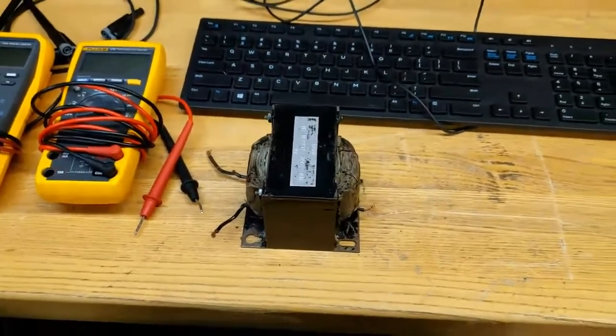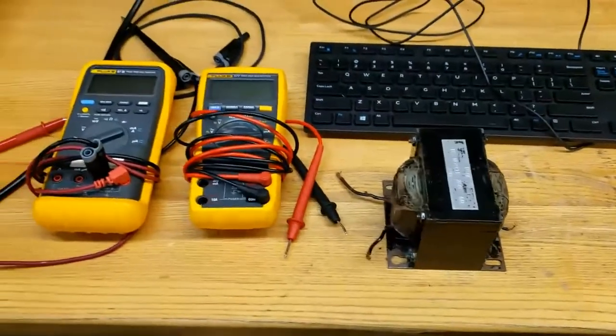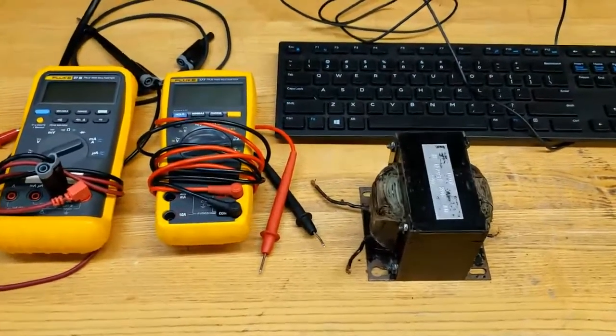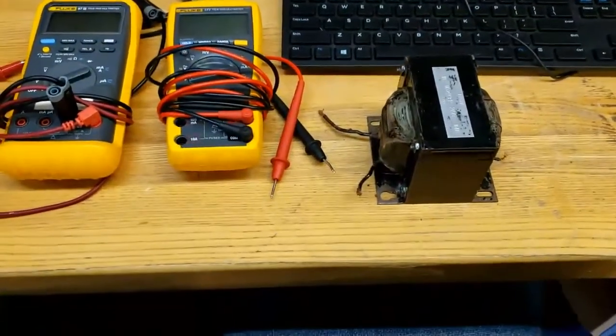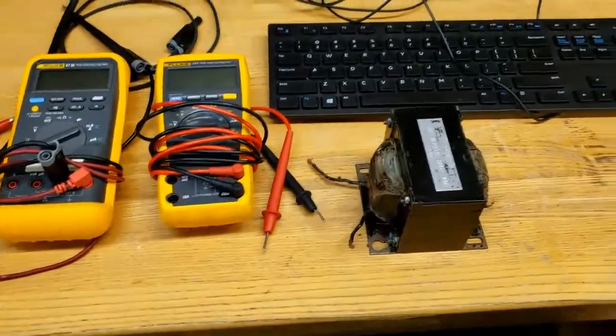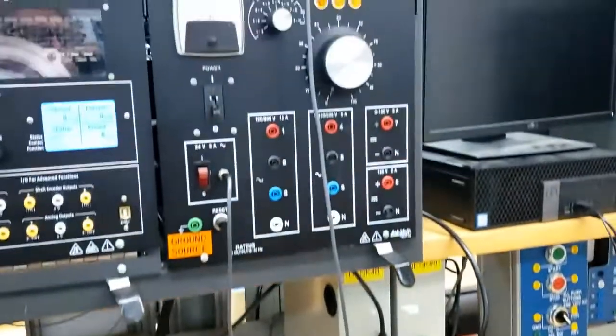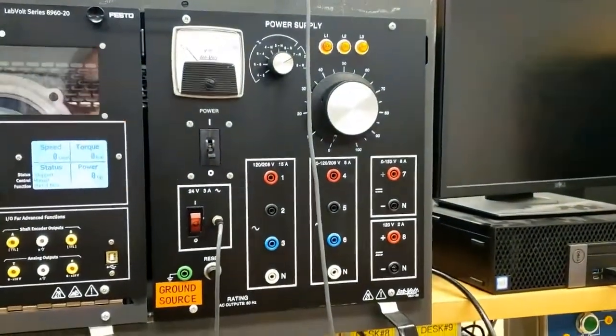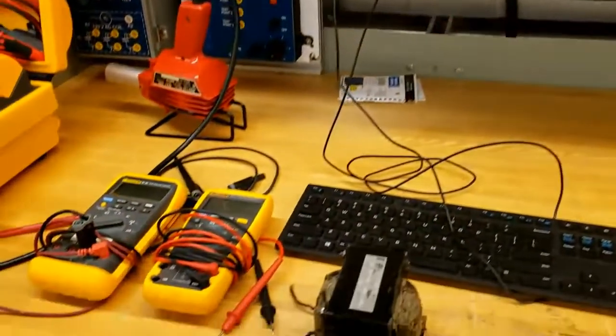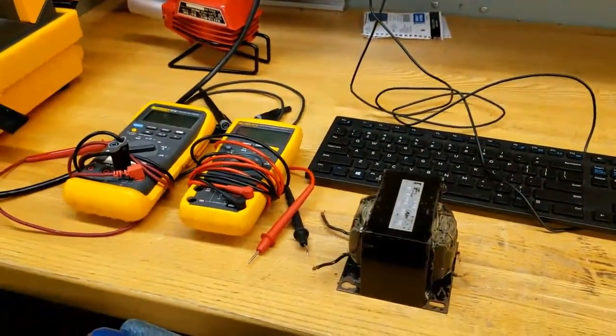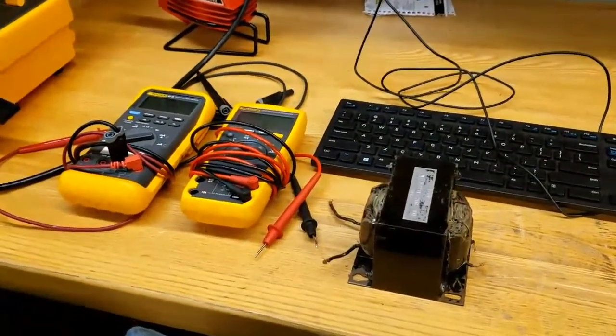At some point, we have to determine when it's safe to put the transformer back in service, and we'll do this by testing it. The basic process is, after I've wet the transformer, you will re-megger it and find that your readings go down from gigohms to megohms or k-ohms.